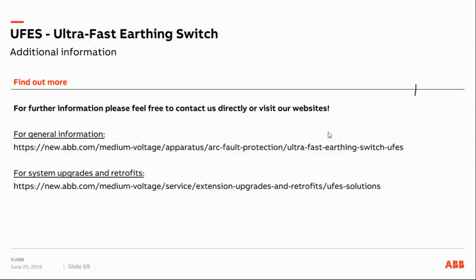Does this rely on the upstream protective device to trip after grounding the system? Well, after grounding of the system, your circuit breaker would take over the rest for fault clearance, so your conventional protection system will take over.